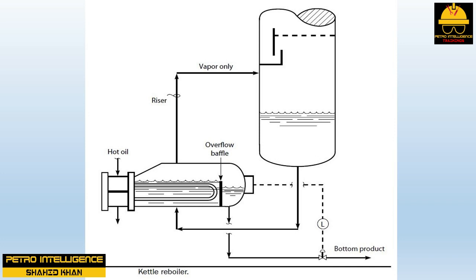Shell-side fouling causes a pressure drop build-up on the shell side of the reboiler, raising the tower bottom liquid level. However, this increased tower bottom liquid level will not be reflected in the indicated bottom level seen in the control room, which actually shows the level at the end of the kettle reboiler. This is a constant source of confusion to operators whose towers flood due to high liquid levels yet their indicated liquid level remains normal.